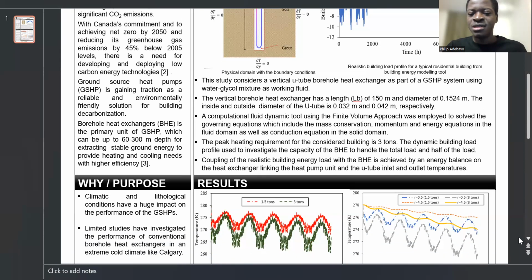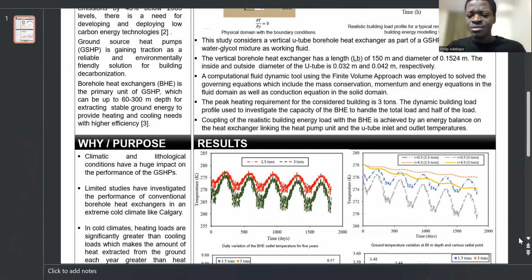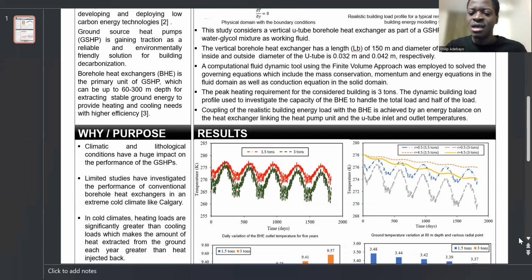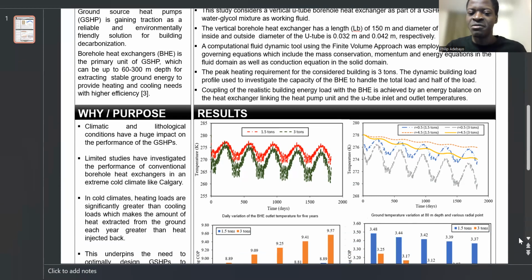So in order to achieve this, we couple the realistic building energy load with the borehole heat exchanger. This is achieved by taking the heat pump unit as a control volume and then performing an energy balance on it, where we have also connected the U-tube inlet and outlet temperature. So from this study, we look at the following parameters, such as the outlet fluid temperature. We also look at the ground temperature variations at the depth of 80 meters and different points, and also look at the coefficient of performance.